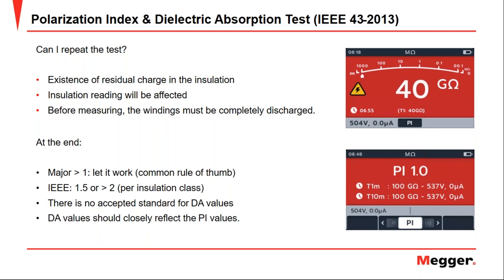If we repeat the test without having discharged the winding, it will give us a wrong value because it is not possible to polarize a material that is already polarized. Although the standard establishes limits of 1.5 and 2 for the PI, when we get values greater than 1 in the field, it is common practice to keep the motor working, because it means the insulation was able to be slightly polarized. In the standard, there is no table of minimum values for the DA. However, it is assumed that the DA limits must be very similar to those of the PI.